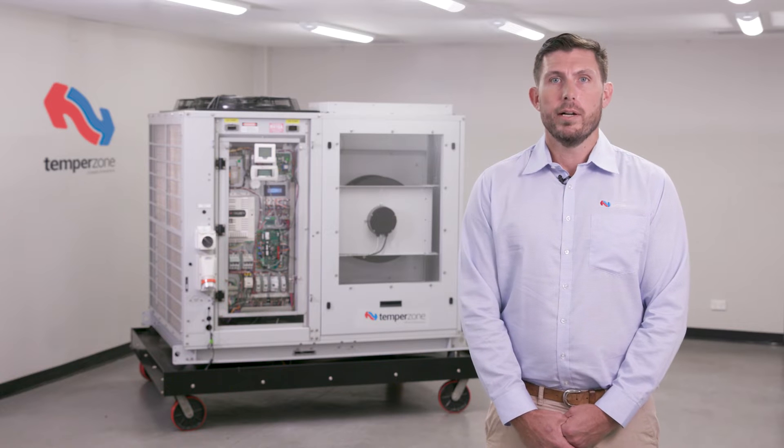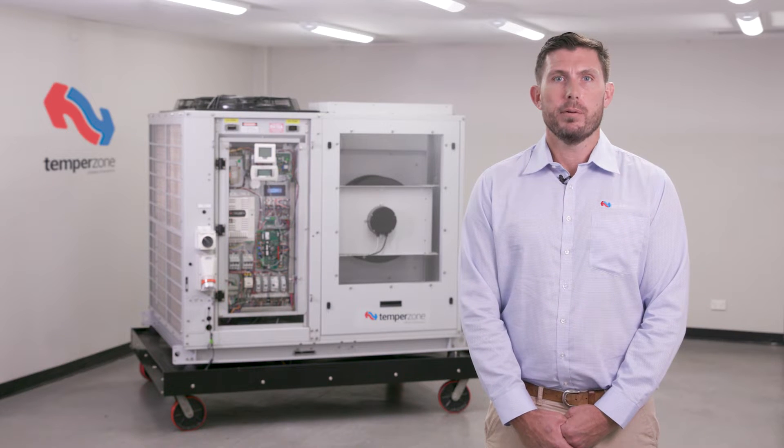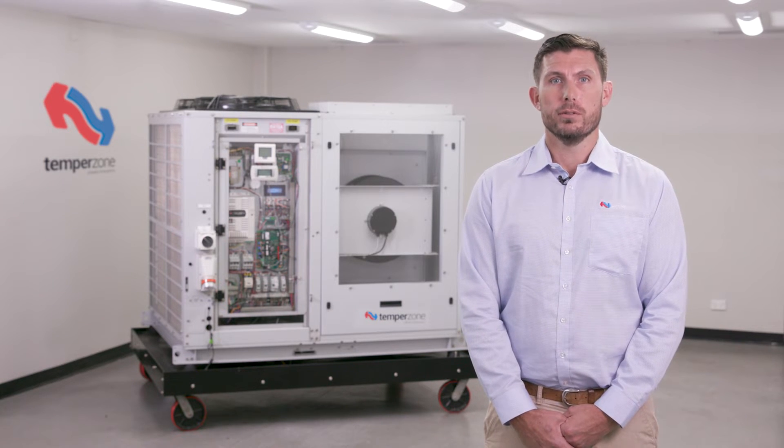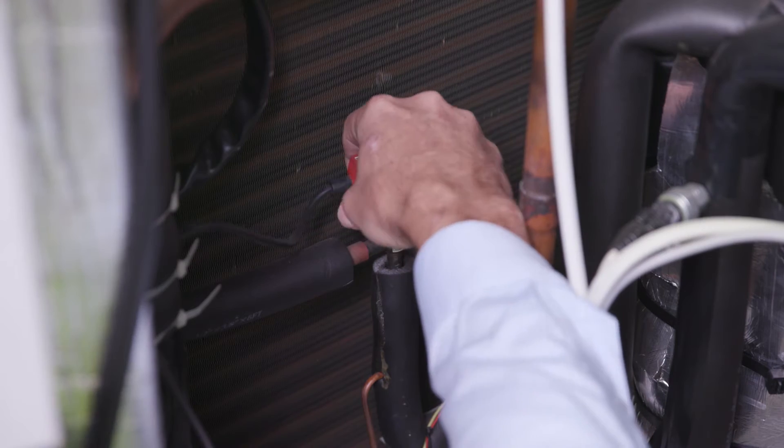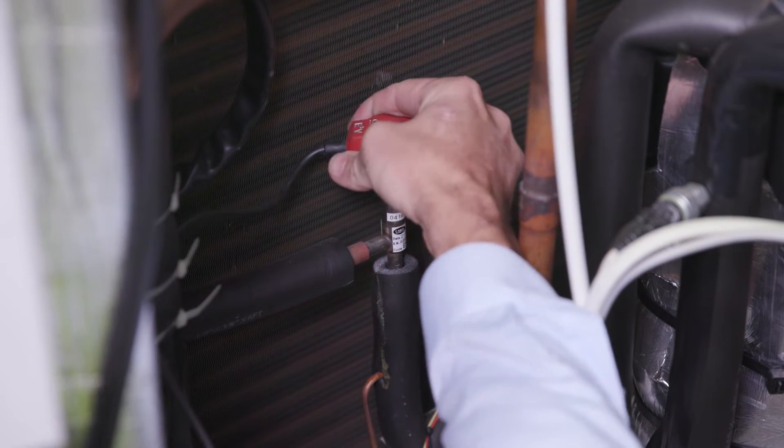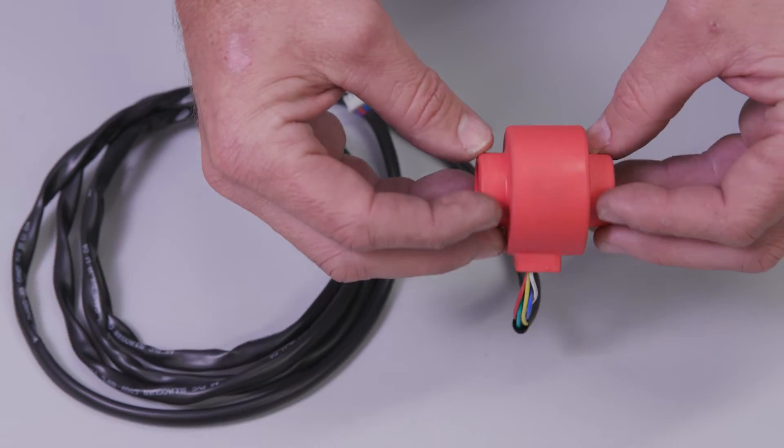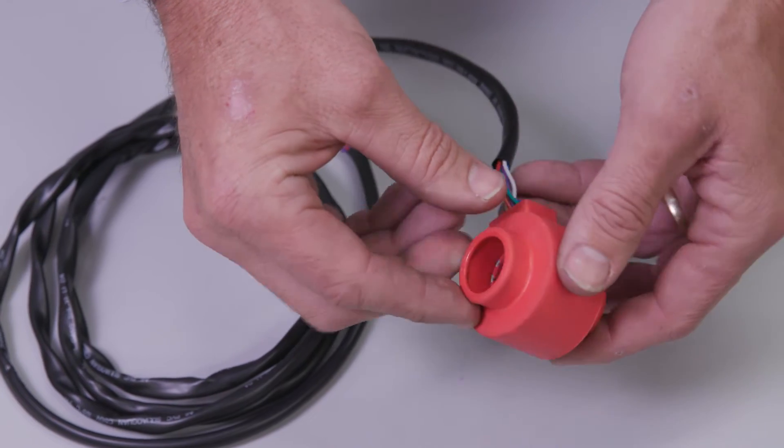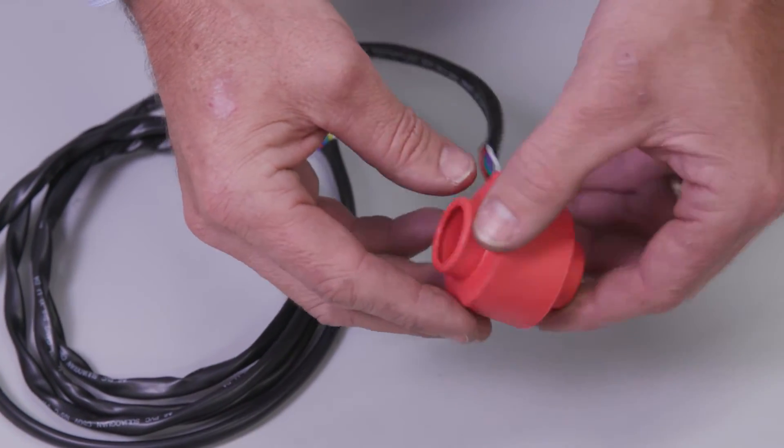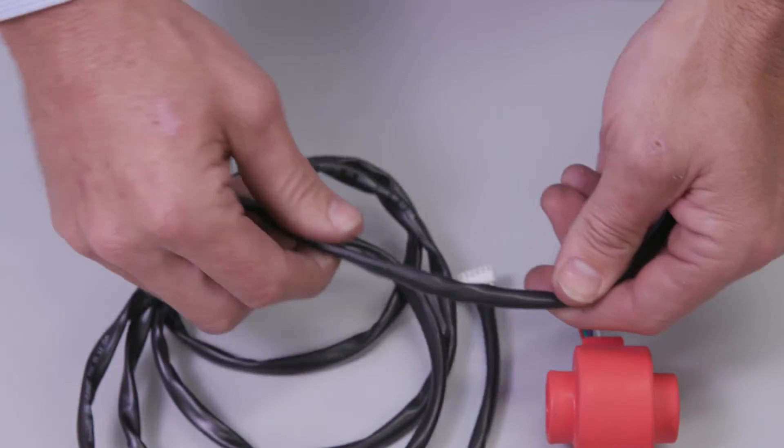EEV failure is a rare occurrence, and an EEV operating incorrectly is usually caused by external circumstances. Before diagnosing valve failure, be sure to investigate the condition of the valve motor, checking for signs of swelling and cracking in the outer casing, and making sure to also inspect motor leads for damage.